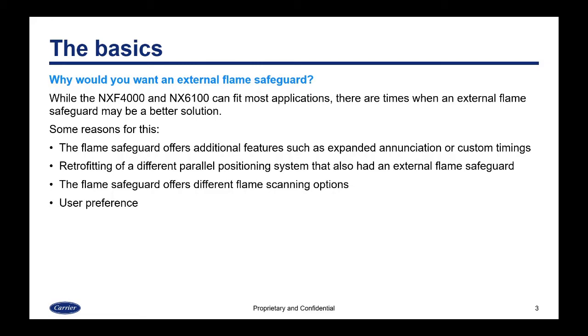So why would you want an external flame safeguard? Well, while the NXF4000 and NX6100 can fit most applications, there may be times when an external flame safeguard may be a better solution. Some of those reasons would be that the flame safeguard may offer additional features such as expanded annunciation or custom timings that the NXF4000 or NX6100 can't cover. Also, it could be retrofitting of a different parallel positioning system that already had an external flame safeguard, and it would be simpler to just replace the parallel positioning system. The flame safeguard may offer different flame scanning options. Or lastly, you might just have user preference. The user may just want them to be separated.